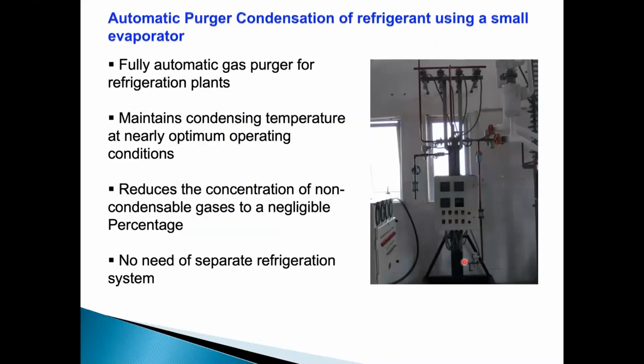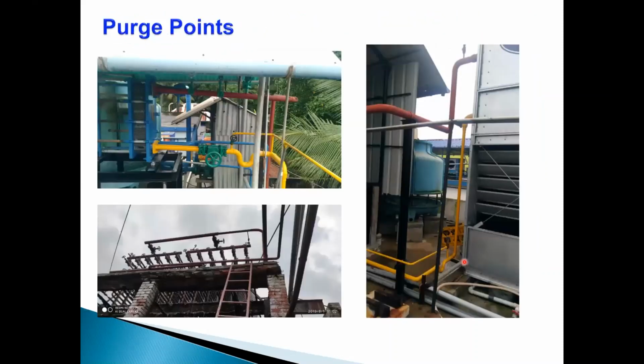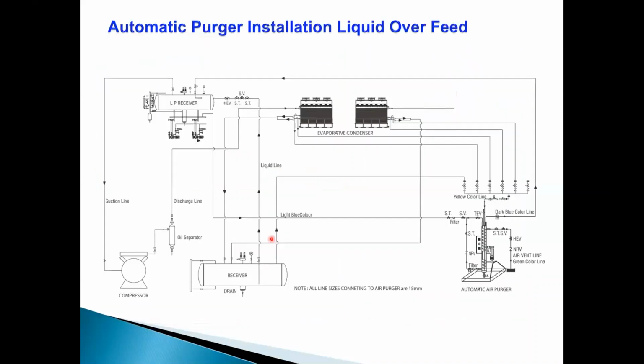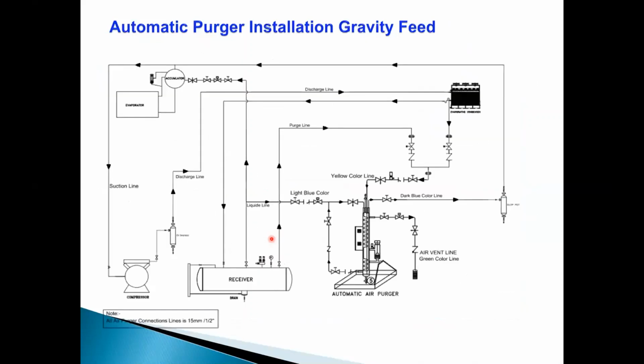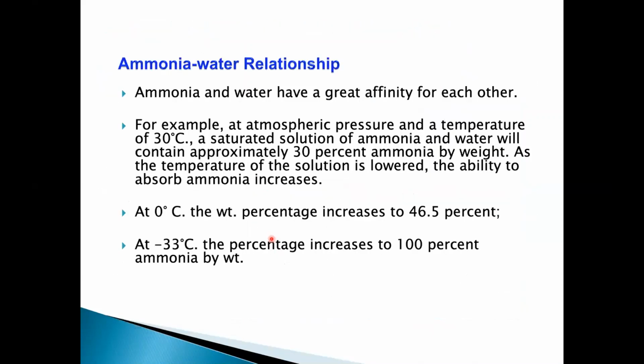This is a typical purger installation. For the purger operations, your purge points are very important and should be taken from the outlet of the condenser. Different applications are shown over here, from the PHE and evaporative condenser to even your atmospheric condenser. Everywhere it can be used. These are some of the installation drawings of the purger. I will not explain in detail because we have limited time available.